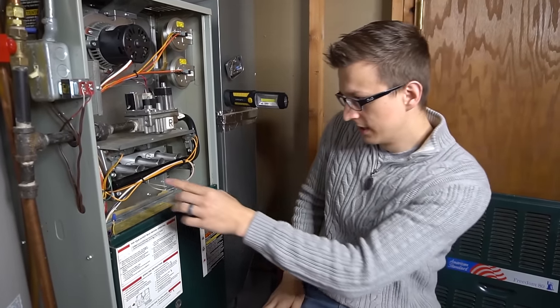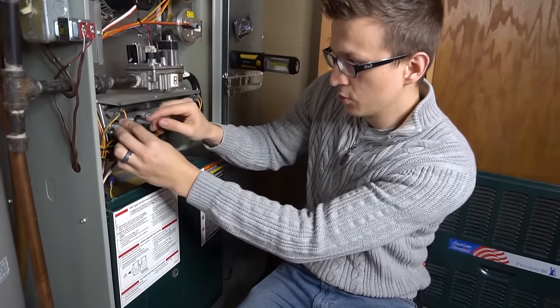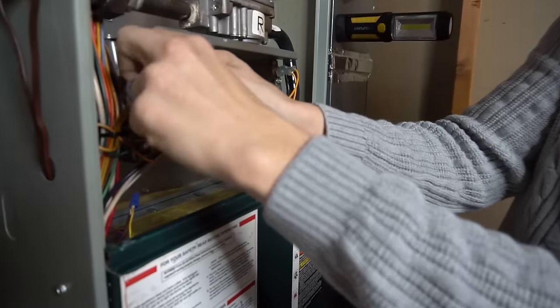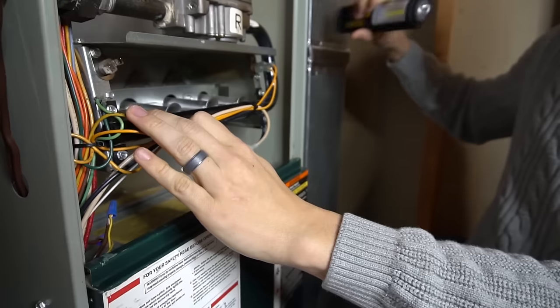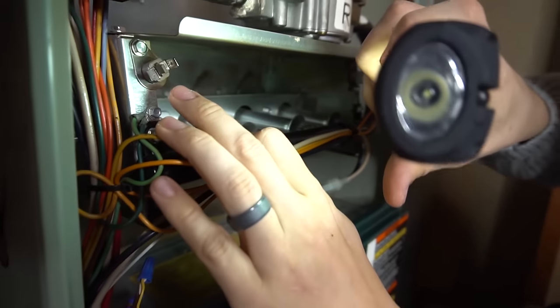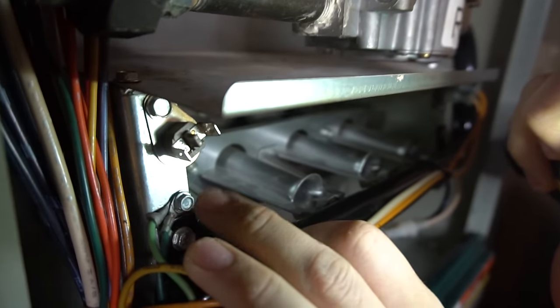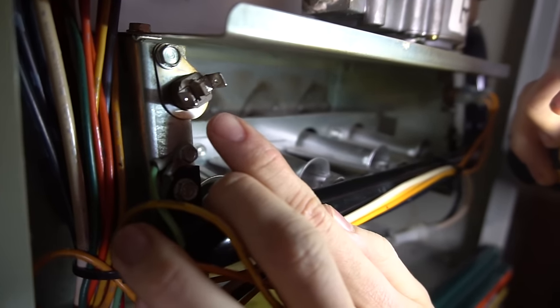The flame rollout switch is this little guy right here. Usually it's just a little switch. I'll just unplug mine so you can see it. That right there is the flame rollout switch, and they are manual reset.